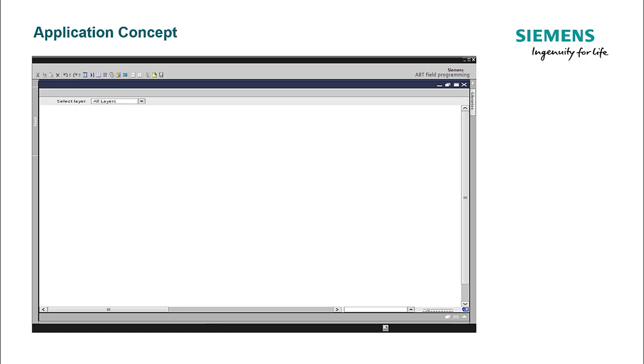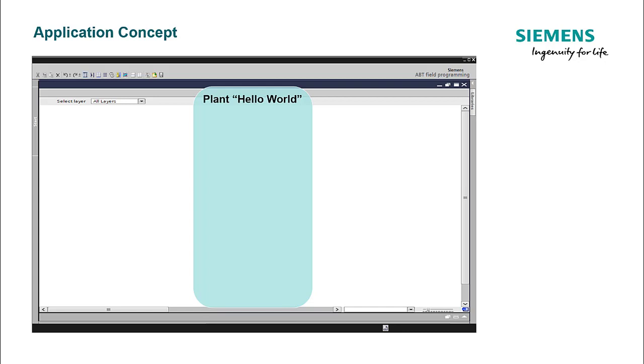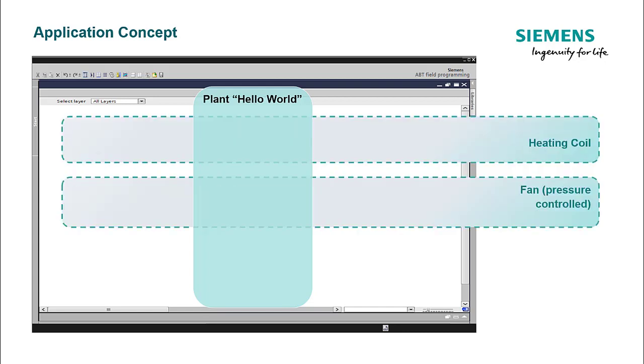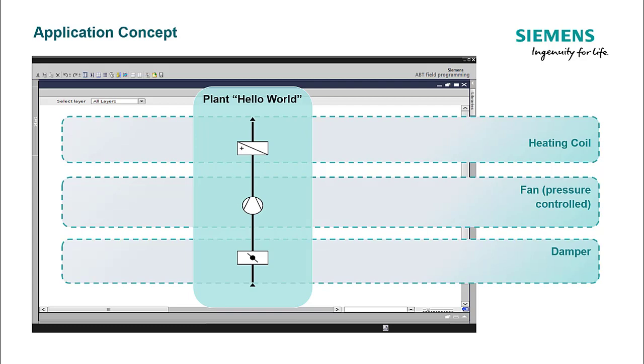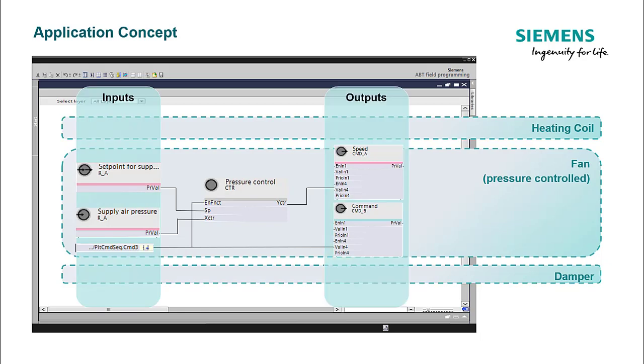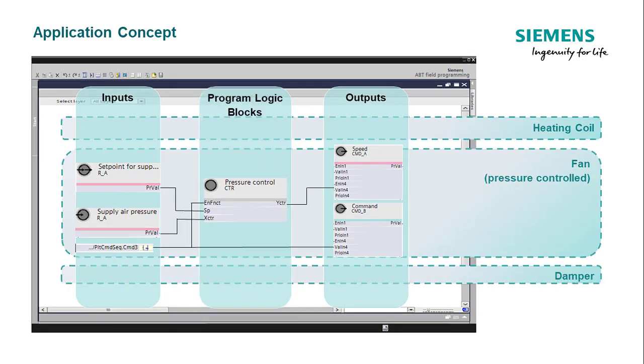This is how the simplified air handling unit 'Hello World' — one of the plant examples from the library — looks like. It consists of three stripes depicting three aggregates: a damper, a pressure-controlled fan, and an electric heating coil. We expand the fan to show the vertical grouping of the function blocks. The inputs are arranged on the left and outputs on the right, with the program logic blocks in the center, ensuring a systematic data flow representation.